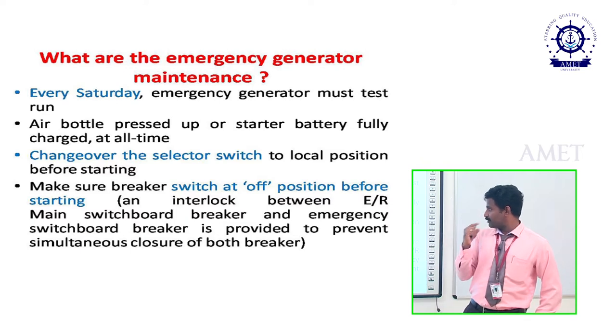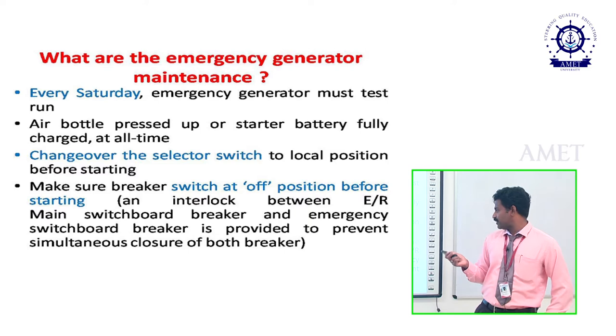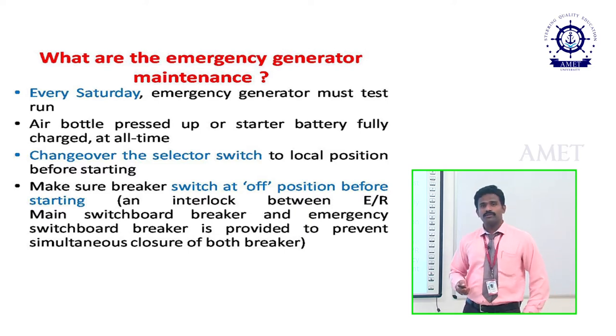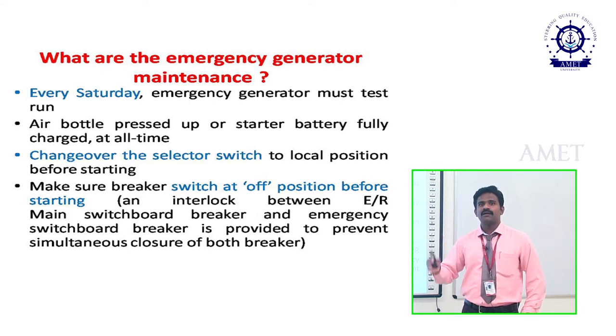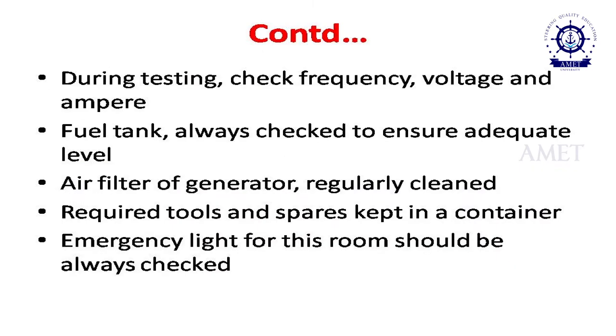Before testing the emergency generator, we must change over the switch from the main switchboard. Also, make sure the breaker switch is in the off position before starting. The interlock between the main switchboard breaker and the emergency switchboard breaker is provided to prevent the simultaneous closure of both breakers. Before going to test the emergency generator on Saturday, we must switch off the starting interlock switch, then after switching on we can check the voltage, frequency, and ampere rating.